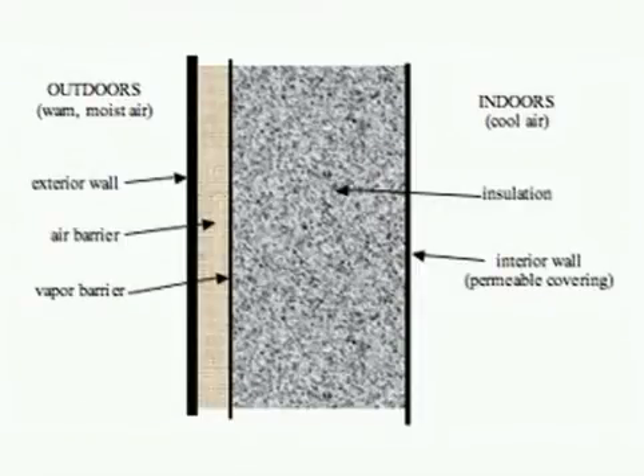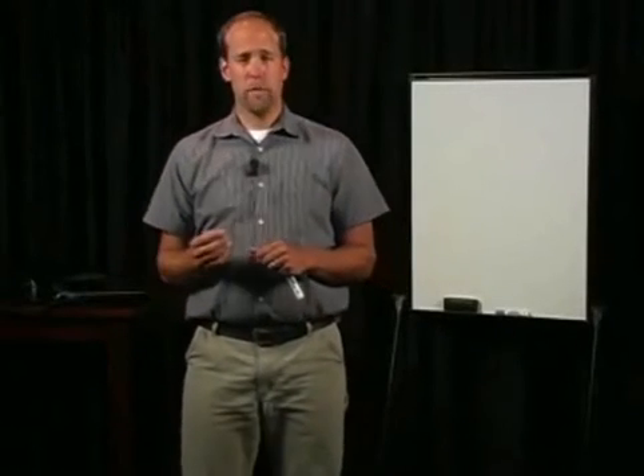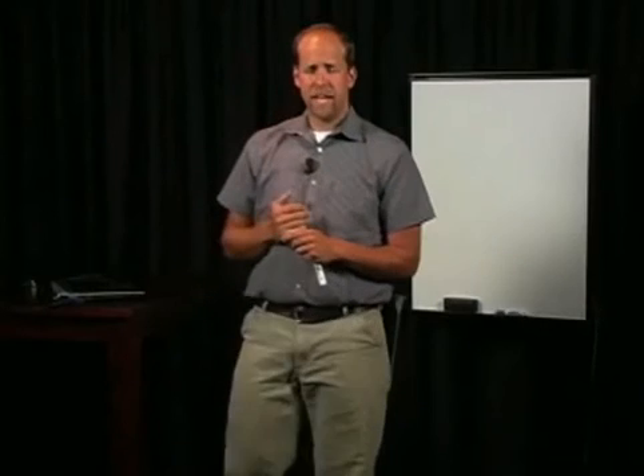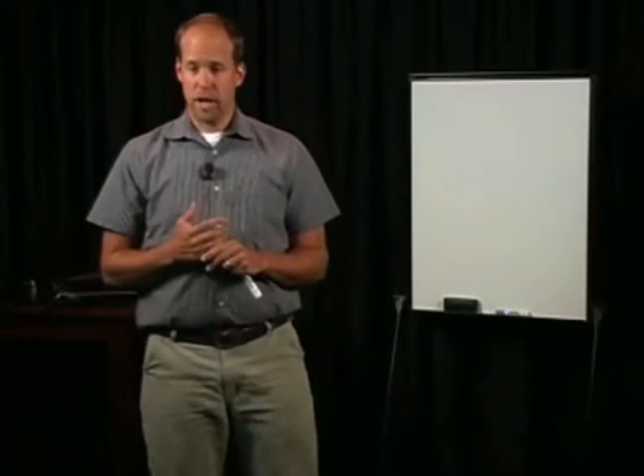Well, to control condensation in a building exterior wall in hot, humid climates, install insulation to prevent large temperature differences between air and surfaces. Install an air or vapor barrier on the exterior side of the building envelope. Avoid impermeable vinyl or other wall coverings and use permeable paints and wall coverings on the interior surfaces of the exterior walls. HVAC systems should be producing net positive pressures on the inside of the building with respect to the outdoors to avoid entry of outdoor air inwards. And try to avoid cooling interior spaces below the average monthly outdoor dew point temperature for the climate in which the building is located. In some areas, this may not be possible.